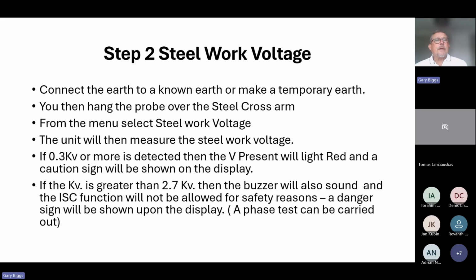So with our unit then, going back to that, we connect the earth now to a known earth, or we make a temporary earth. Now the unit comes with these little pegs, so if there's no known earth that you can connect to, you can put a peg into the ground and make a temporary earth and connect your earth to that. You then take the probe and you hang that on the steel cross arm. Now the probe itself is terminated at the top end with a little hook. So you hook the probe over the steel cross arm. Now the probe is essentially made as a Bowthorpe rod, and anybody working upon these sort of systems would generally have their earth rods that they use for earthing out when they're working, and they would use those rods to attach the probe to the steel cross arm.